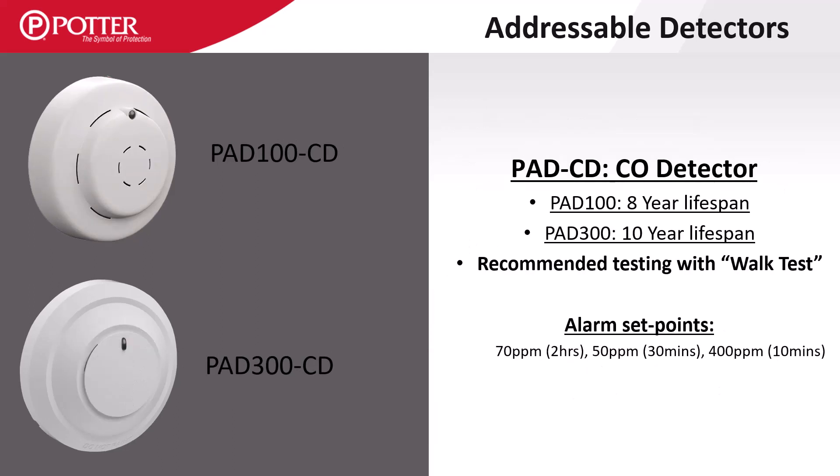On the PAD CD carbon monoxide detectors, there is a difference in lifespan between the 100 and 300 series detectors. The PAD 100 has an 8 year lifespan, while the 300 has a 10 year lifespan. Because CO detection requires threshold timers, it is recommended to test Potter's CO detectors with the control panel in walk test mode. This disables the timers and allows a quick response to CO test gas.